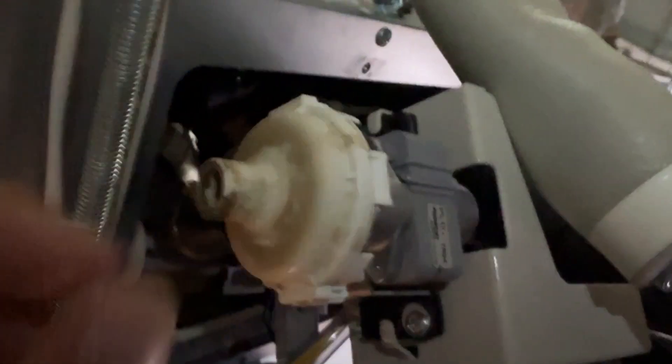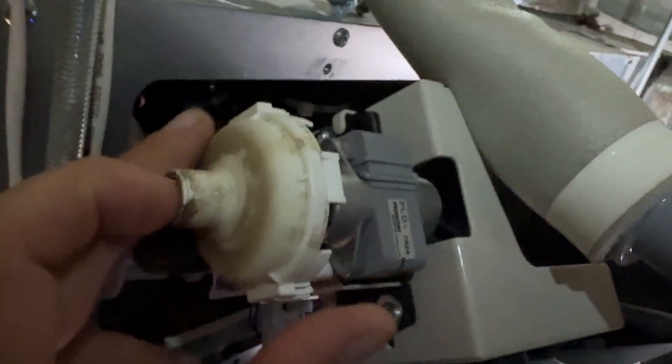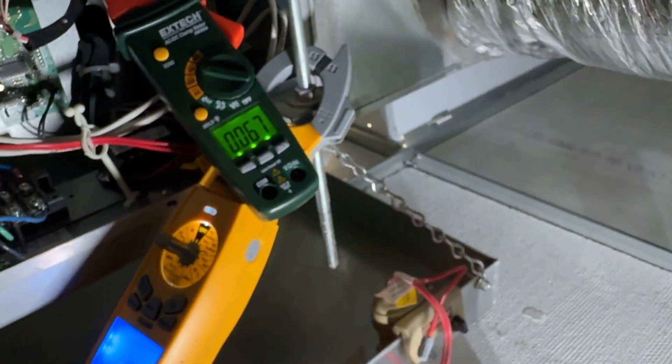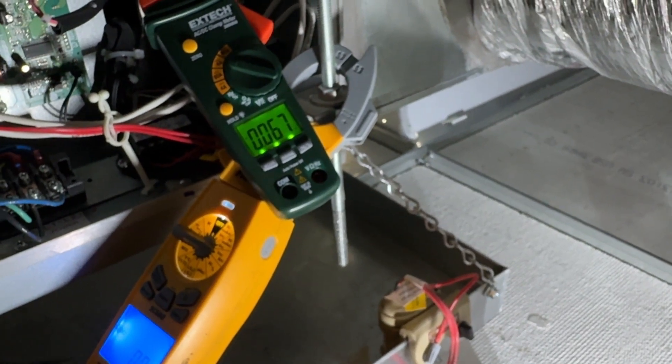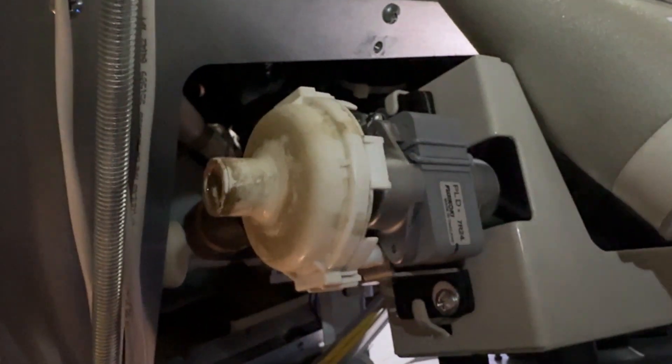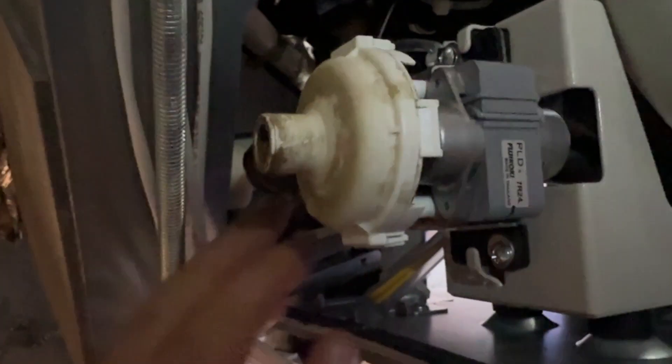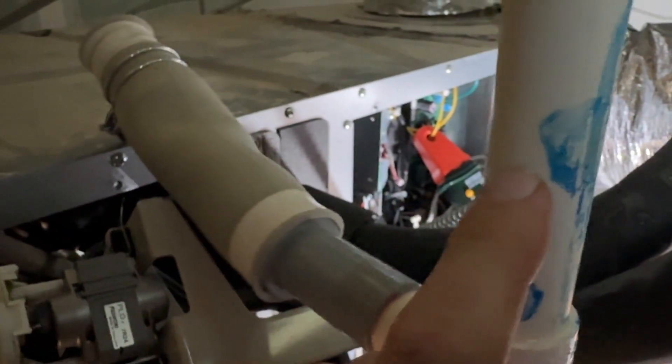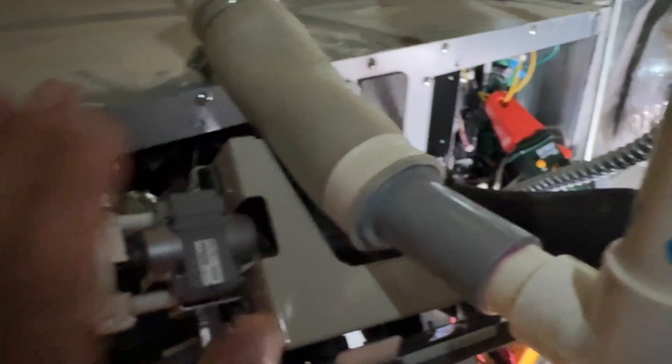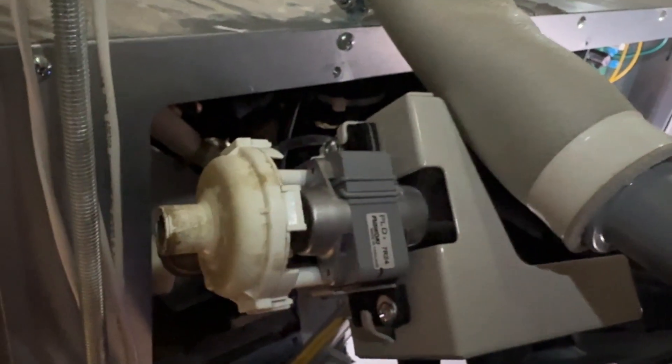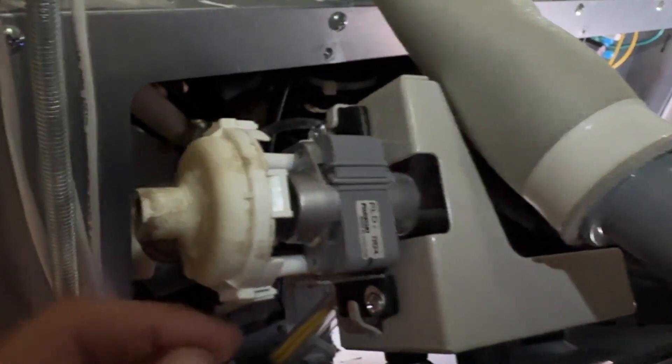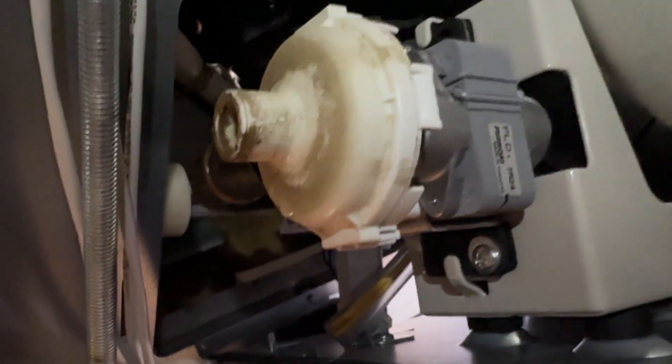Now I'm gonna see what it does when we jam it up. Alright good to know. I think this is just a situation of this maybe being too tall causing issues when this pump shuts off. I need to look at the spec and see if this is even acceptable. But either way it's struggling to get the condensate out. It doesn't look like the drain is clogged.